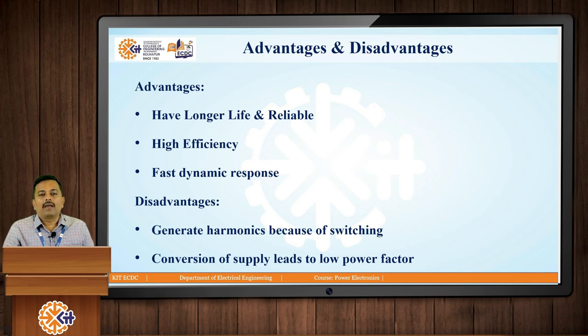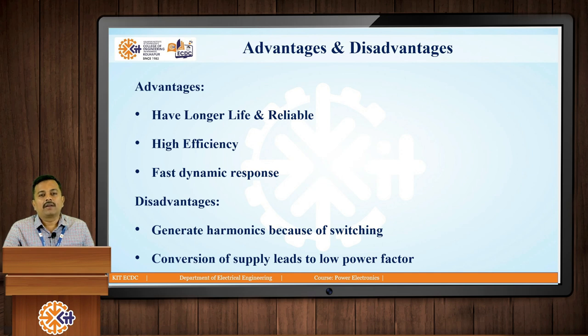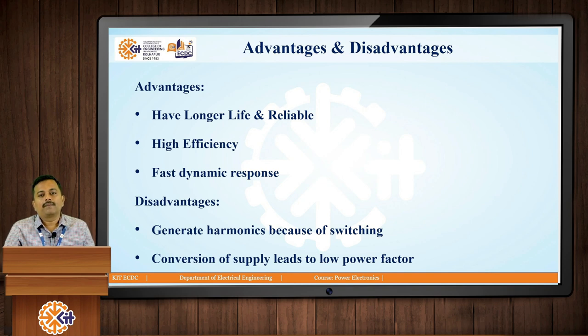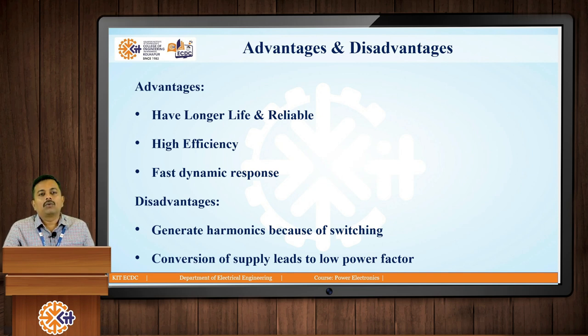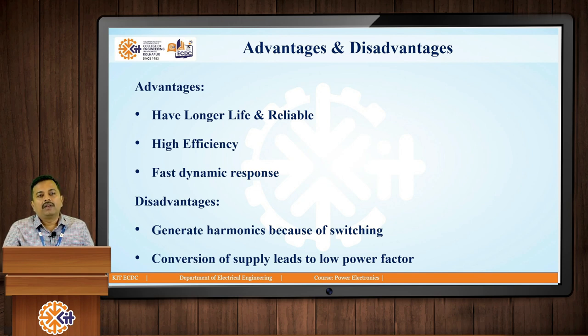Also, conversion of supply leads to low power factor. The disadvantage of low power factor is that the circuit starts drawing a large amount of current from the source. As the current drawn is of a higher level, we have to pay more electricity bill for the same load. This power factor can be improved with the help of a capacitor connected in parallel with the circuit, which acts as a power factor improvement device. The harmonics generated during switching can be eliminated by connecting tuned filters, which consist of inductors and capacitors.